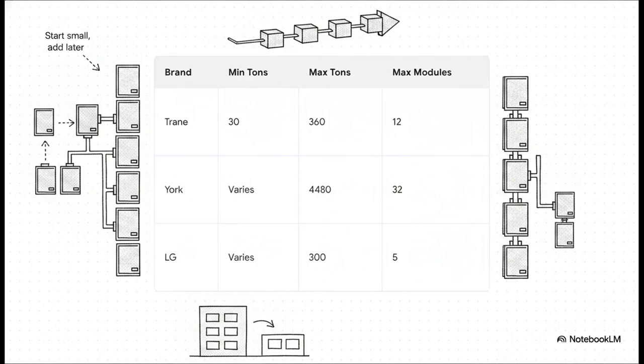And that translates directly into massive scalability. Whether you need just 30 tons to start or you're scaling all the way up to York's massive 4,480-ton capacity with 32 modules, you only install what you actually need today. Take a manufacturer like Trane, for example. Their ThermaFit line lets you start at 30 tons and expand to 360 tons by linking up to 12 modules. LG lets you scale up to 300 tons with 5 modules.